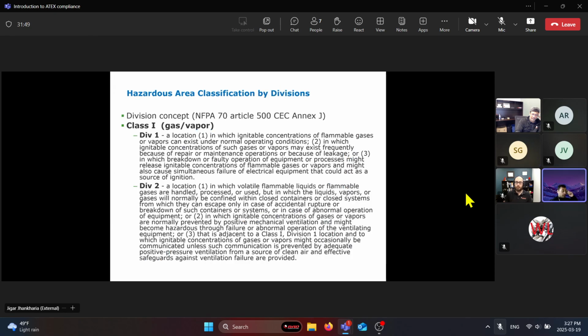Coming back to division, pretty much, it says Division 1 refers to Zone 1, a location in which ignitable concentrations of flammable gases or vapors can exist under normal operating conditions, in which the concentrations of gases, vapors may exist frequently because of repair or maintenance operations or because of any leakages. So again, it reflects the same as Zone 1. Division 2 reflects the same as Zone 2. So Division 1 counts as Zone 0 and Zone 1 in this case.